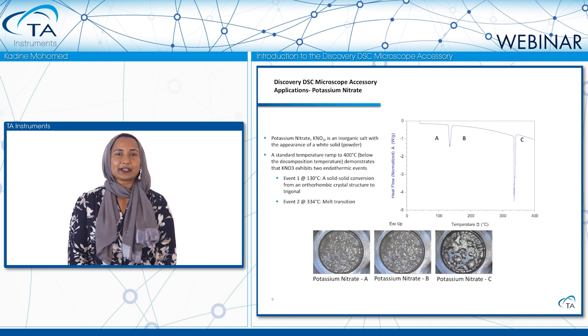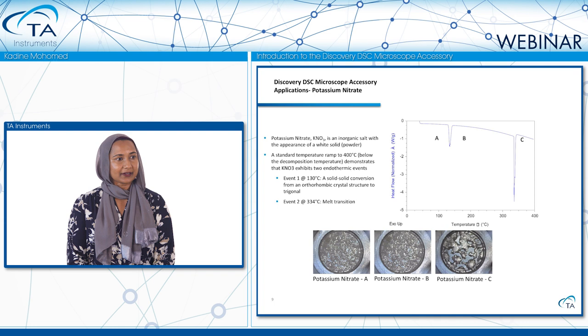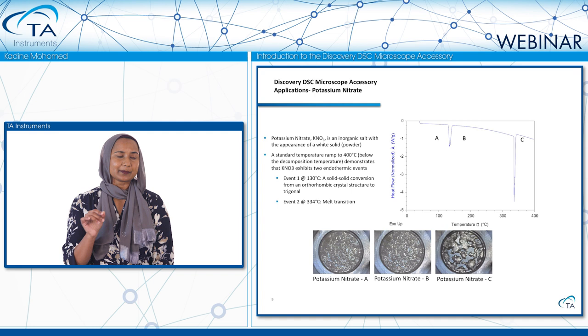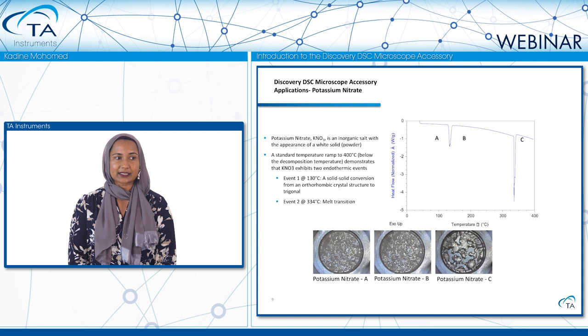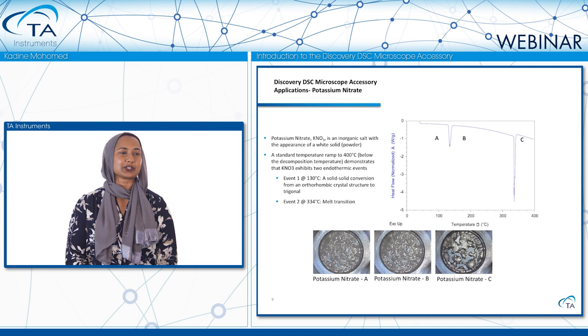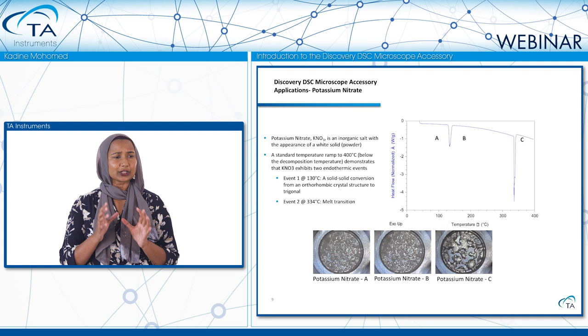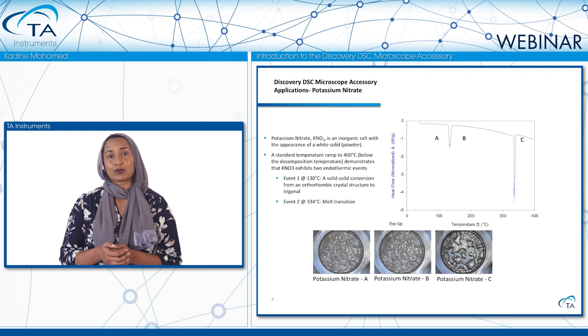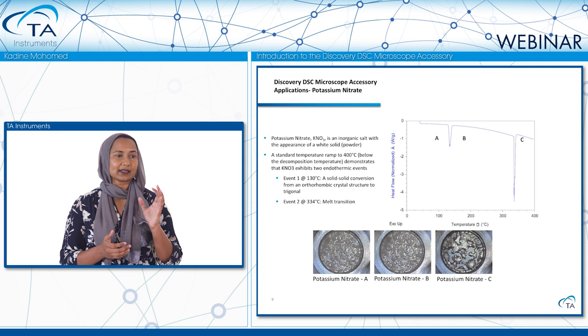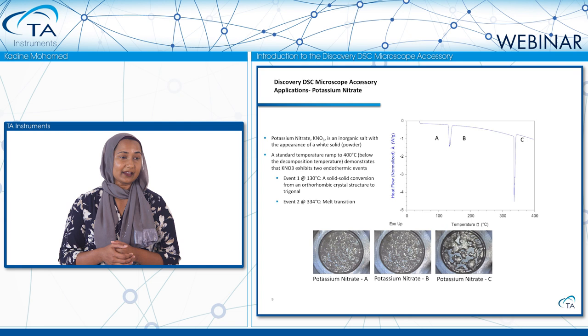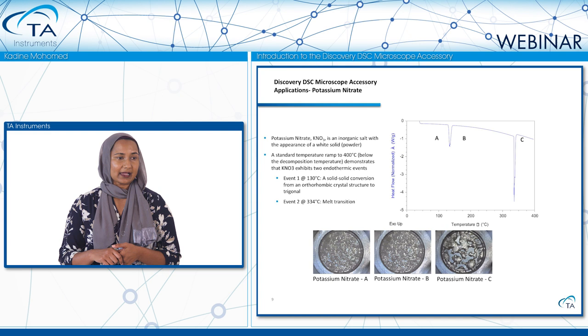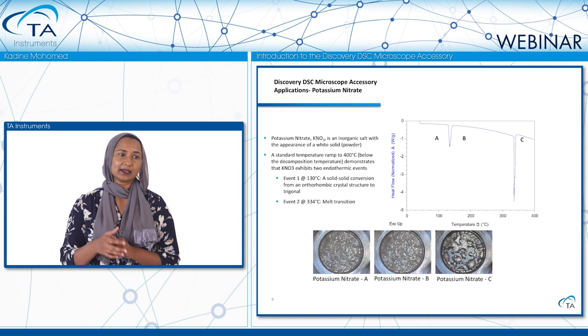The next example is potassium nitrate, an inorganic salt with the appearance of a white solid powder. As we begin a temperature ramp at 10 degrees C per minute to 400 degrees, we see two endothermic peaks. I've labeled the region before the first peak as A, after the first peak as B, and after the second peak as C. Without additional information, it would be difficult to determine whether A to B is a melt and B to C is decomposition, or whether A to B is a solid-solid phase transformation and B to C is an endothermic melt.